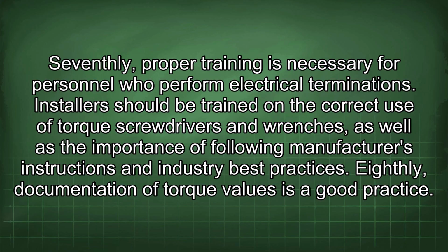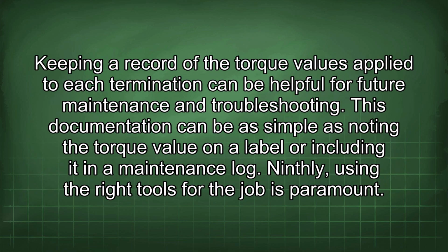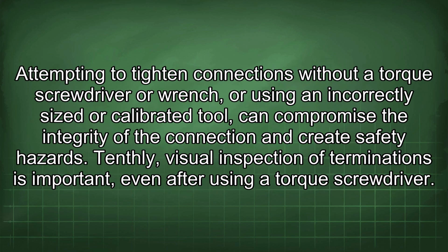Eighthly, documentation of torque values is a good practice. Keeping a record of the torque values applied to each termination can be helpful for future maintenance and troubleshooting. This documentation can be as simple as noting the torque value on a label or including it in a maintenance log. Ninthly, using the right tools for the job is paramount. Attempting to tighten connections without a torque screwdriver or wrench, or using an incorrectly sized or calibrated tool, can compromise the integrity of the connection and create safety hazards.